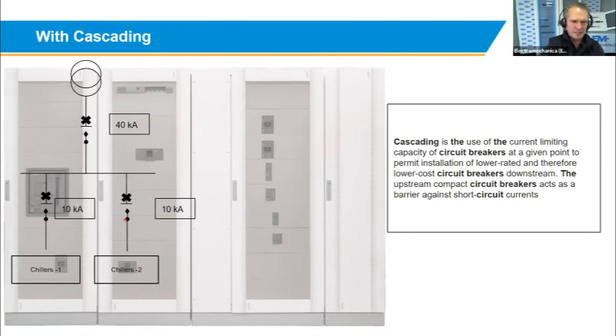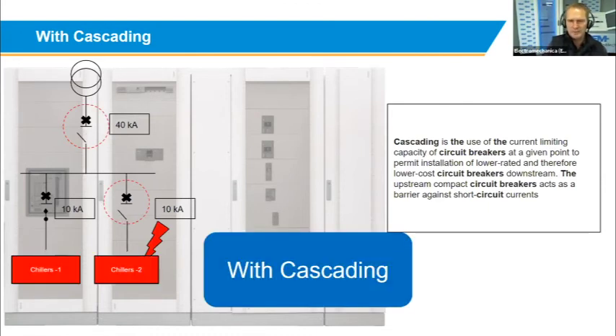So let's say a short circuit occurs there. What will happen? There's no time for a bimetal to heat up or anything. It just happens immediately. Both these breakers will open, and the majority of the short circuit will be in the molded case circuit breaker that can actually handle 40,000 amps, keeping this breaker safe and protected. So this is the reason you will use cascading.